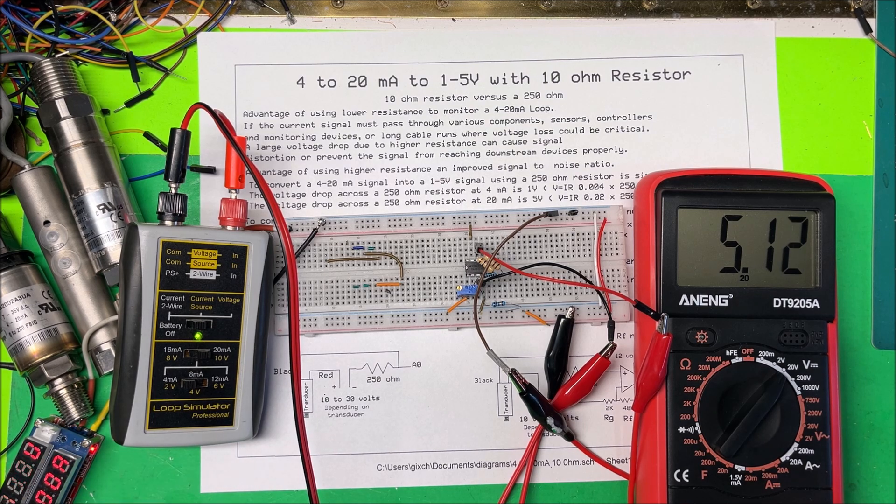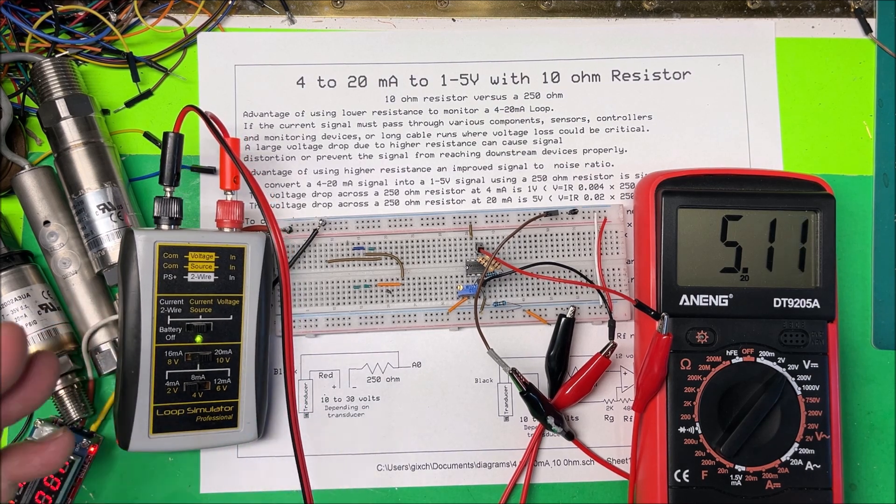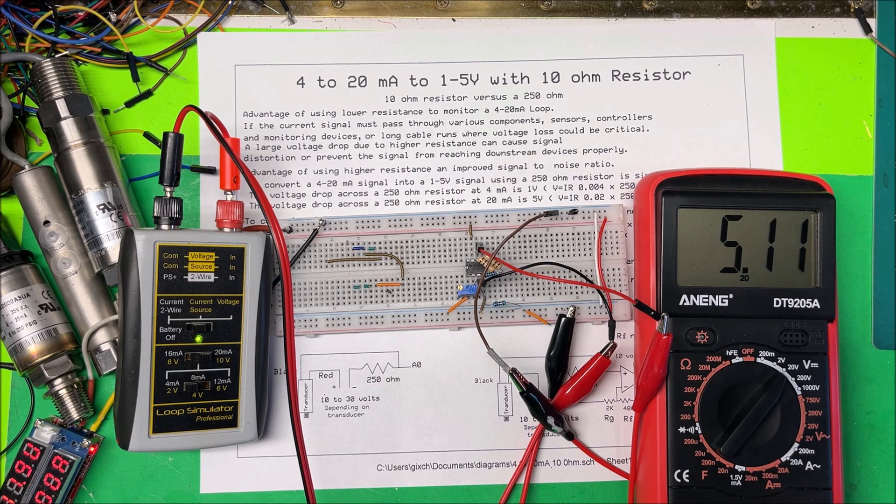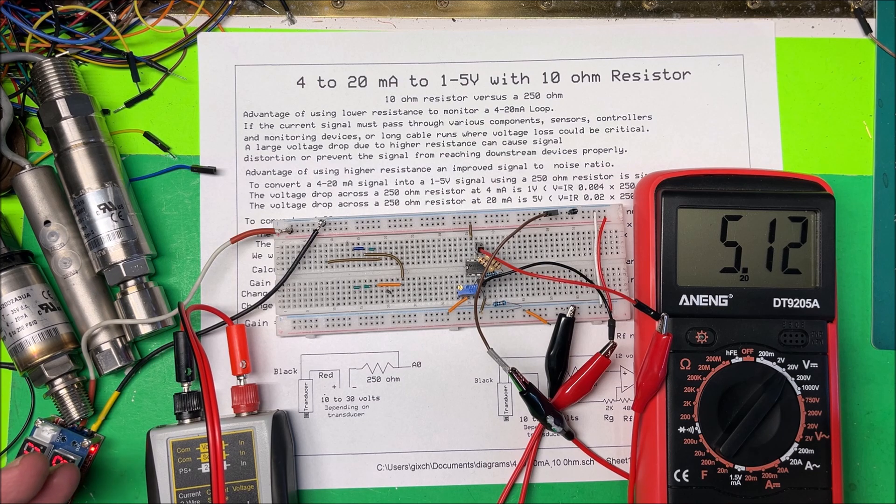But I go from 1 volt to 5 volts, okay. So it works with the 10 ohm resistor. Most of the time you're going to use a 250 ohm resistor, that's going to be a lot better, but if you had to you could use a 10 ohm resistor for that. Anyway, that's the 4 to 20 milliamp loop with the 10 ohm resistor. Thank you.